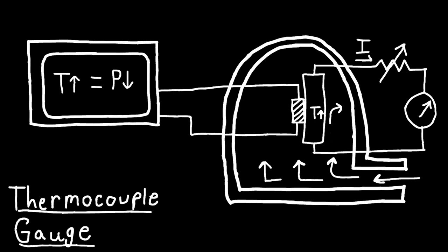by the thermocouple element. In the high vacuum regime, the mean free path is now long enough that the gas molecules spend much more time interacting with the walls of the chamber than each other. In this regime, we refer to the flow as molecular. In order to pump gas in molecular flow, more complicated systems are necessary.